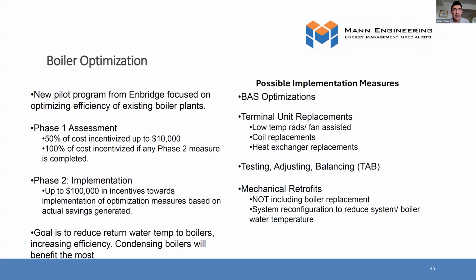You actually have to change how you operate the boiler system, and potentially you have to do design changes to the building or the mechanical system itself in order to actually achieve the efficiencies that you think you're going to get. So I've seen lots of cases where condensing boilers have been installed where they're not getting any additional savings, but they've spent a lot of money on the new condensing boilers, and it also comes with higher maintenance costs too. So this program is really designed to look at those systems where there's potential for savings just through optimization of the boiler system. So the main goal here, like I said, is to reduce the water temperature that's going into the boilers so that we can actually get to condensing efficiency.